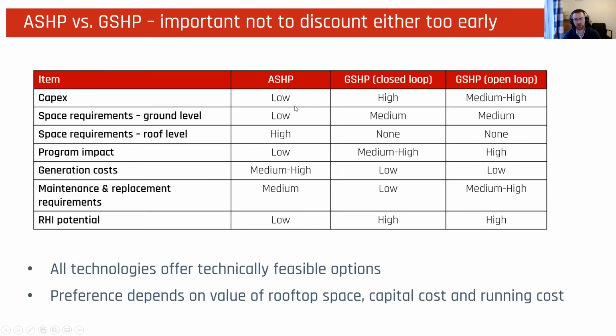So the differences we're looking at is, in general, air source is going to be a lower cost solution than ground source. However, we're going to need more rooftop space or more plant room space to make that possible, which in some developments is just simply not an option. Ground source is going to have much higher impact on your construction program than air source, and open loop is going to have probably significantly more program impact than closed loop due to the permitting and environmental agency permitting requirements that are associated with that.